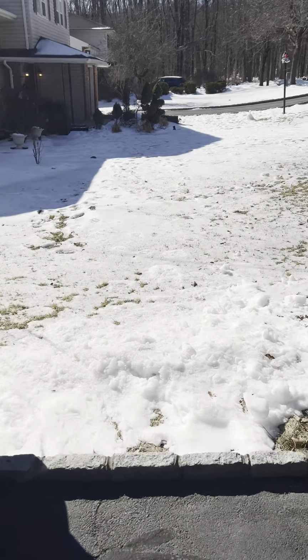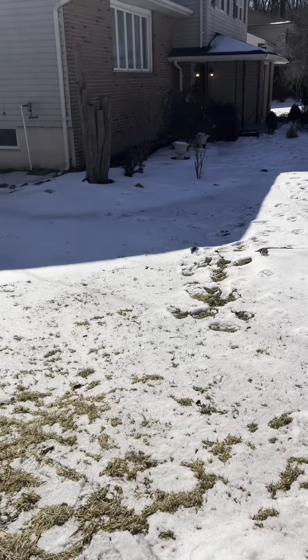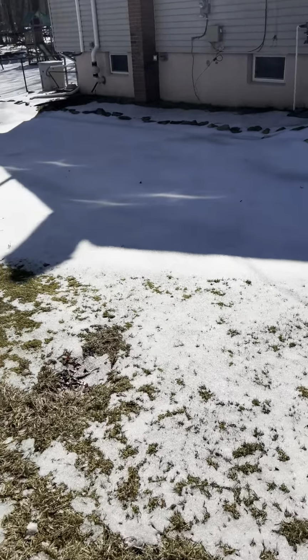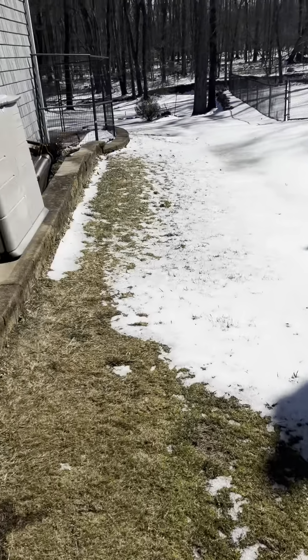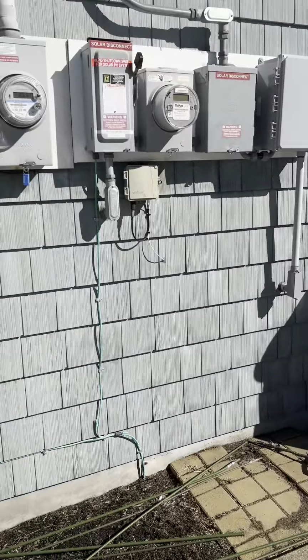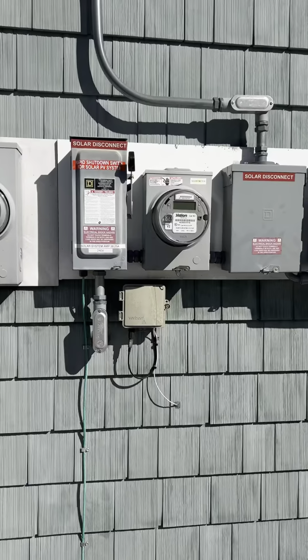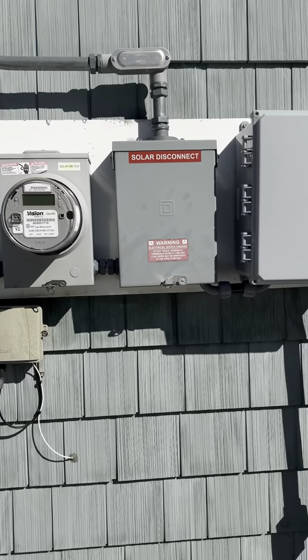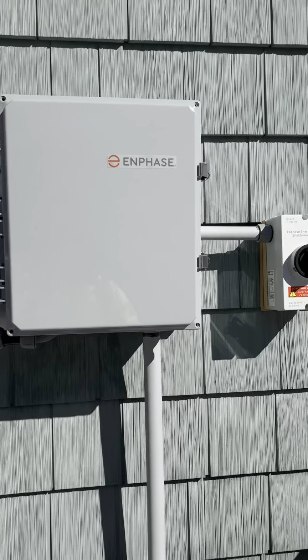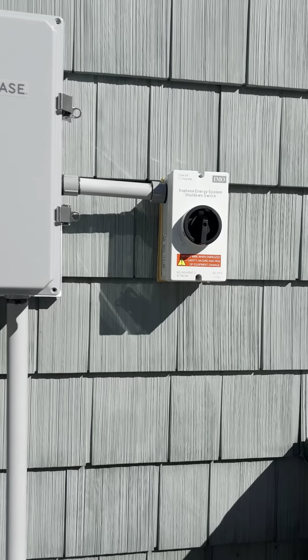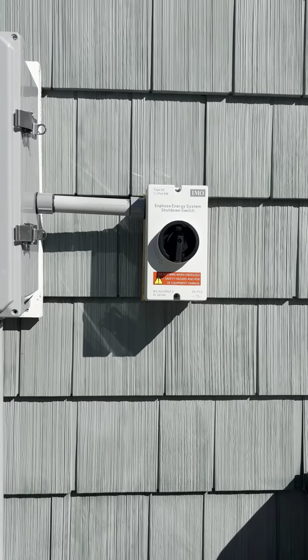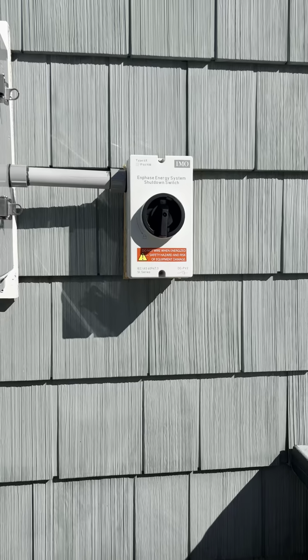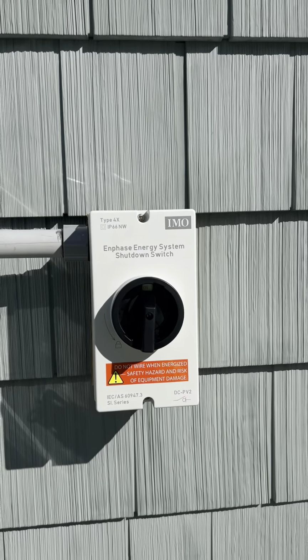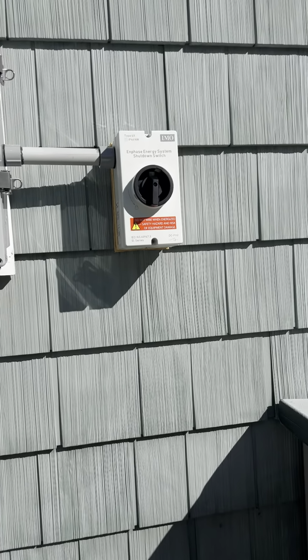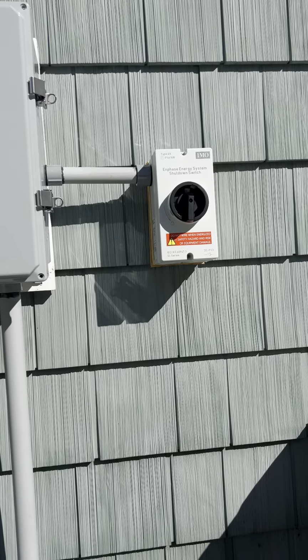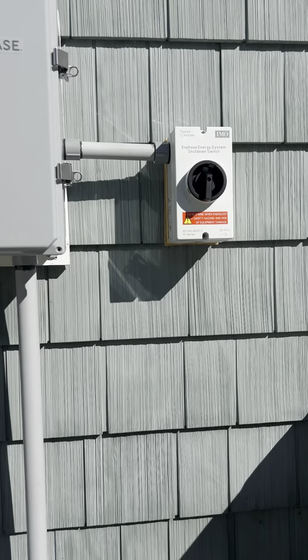So here on the back side of the house, we have our 40 amps of solar, about 36 panels, or 34 panels rather, and it's the legacy microinverters, the M215 microinverters. We have a rapid shutdown switch here. This is all included in the Enphase System Controller 3. And pretty much this shutdown switch disconnects and opens all the relays for the PV, the solar panels and the batteries.